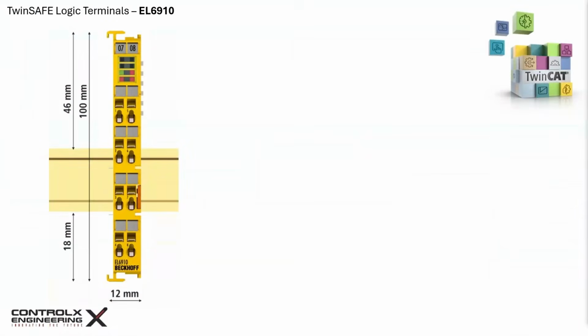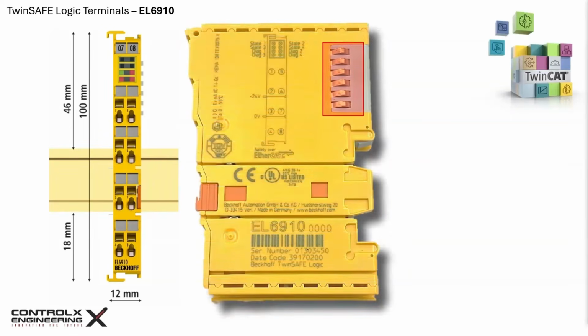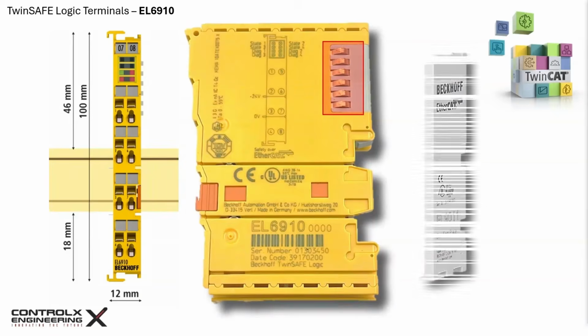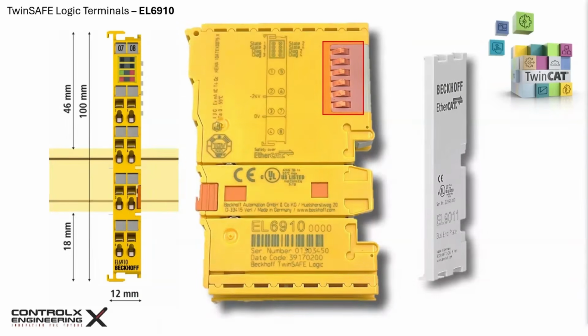These are the dimensions of the terminal when mounted on a standard 35 mm DIN rail. When installing inside a control cabinet, the recommended protection rating of the cabinet must be IP54 or higher in accordance with IEC 60529. Always protect the exposed electrical spring contacts with another terminal to the right-hand side or with an end cover, like the EL9011, to ensure the protection rating and for ESD protection of the device.